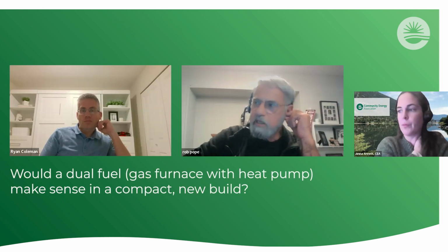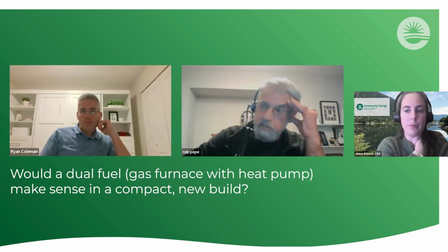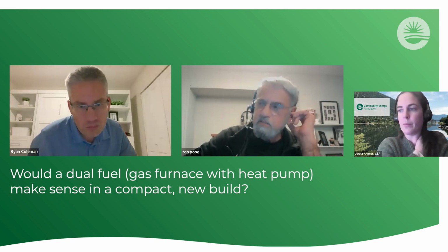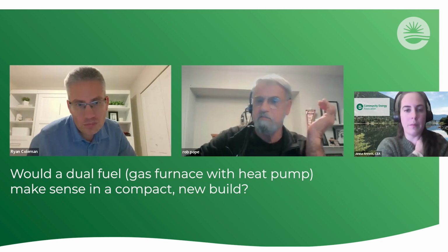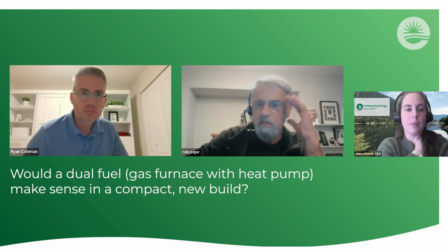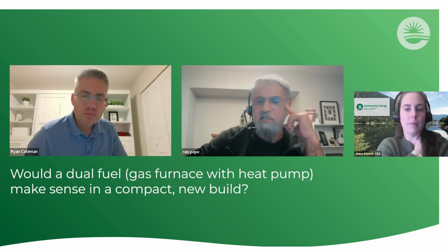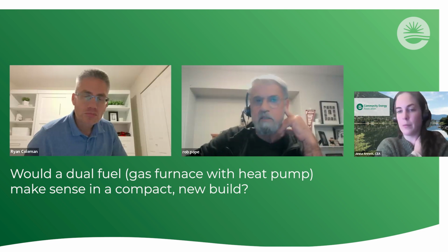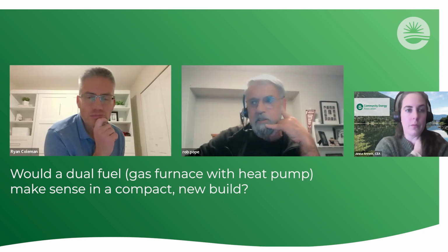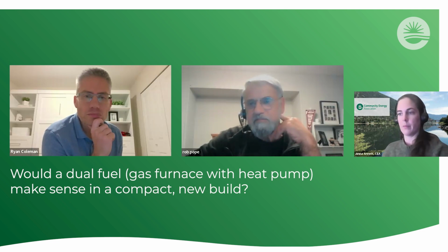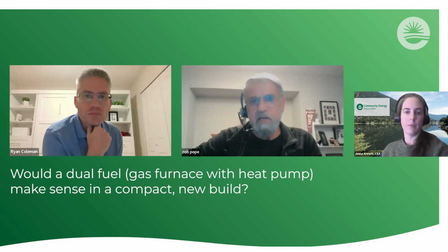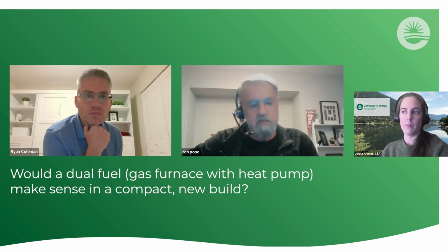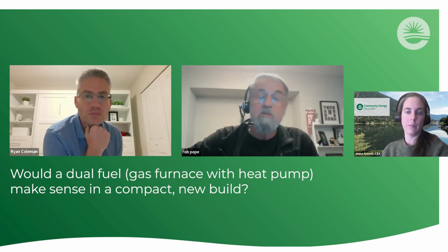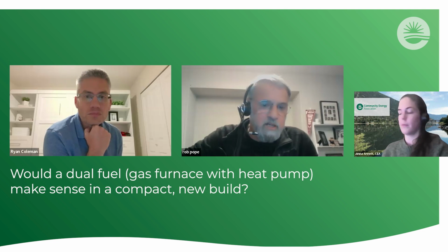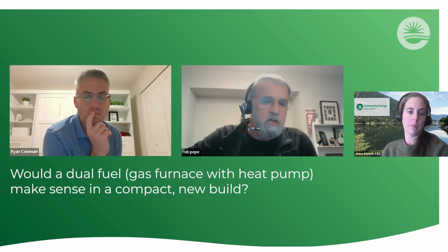It's a good question. Depending on the climate zone, you may be in a situation where there's only a single product in the market right now that does lower than 36,000 BTUs as a gas product. It's a Dettson. So you're limited in the gas products to put in as a dual fuel or hybrid system. My biggest challenge would be how much room I have on the panel. If it's a 200 amp service, how much room do I have for 40 amps, say, or 30 dedicated to the heat pump? And maybe a 10 kilowatt heater strip, right? Which is going to take another 40 amps. If I've got room for that on the panel, the heat pump, probably all electric, would be my first choice.